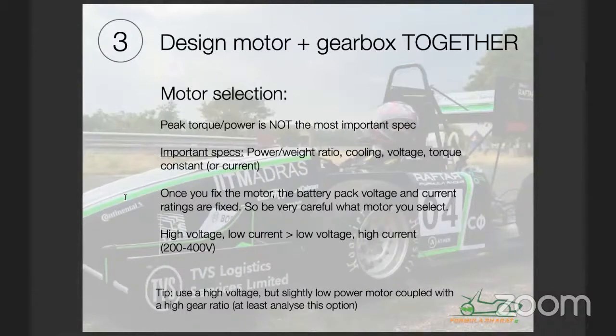Now, the important thing here is once you fix a motor, the motor at a high level is something like, this is a 30 kilowatt motor that operates at 230 volts or 250 volts or 400 volts or something. The moment it's a 30 kilowatt motor operating at 300 volts, that means your rated current is 100 amperes. So once you pick a motor, that already defines the battery pack voltage and the battery pack current rating.